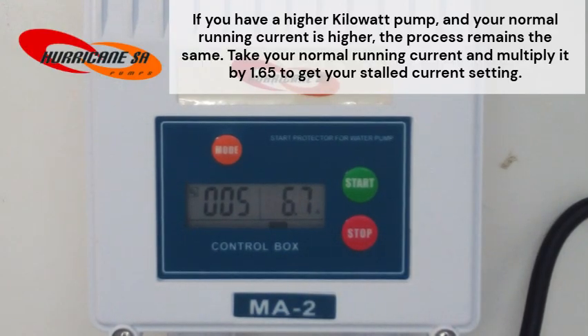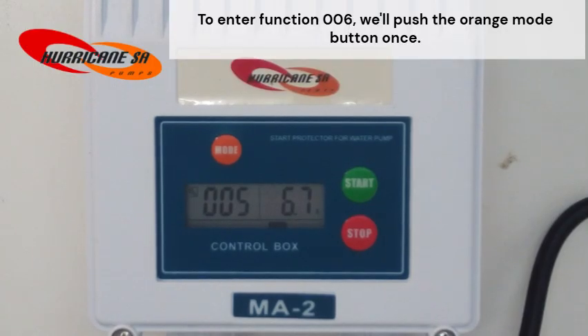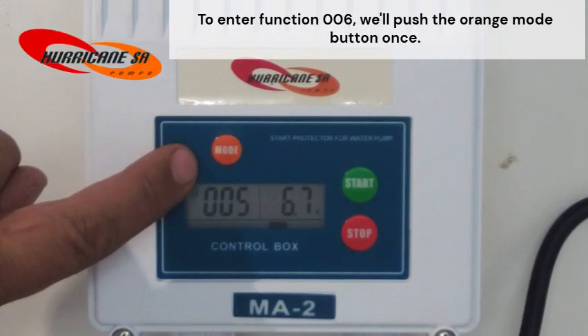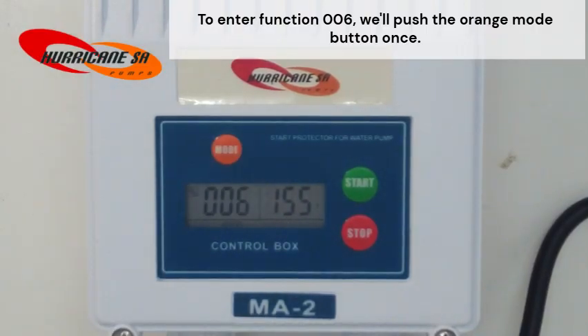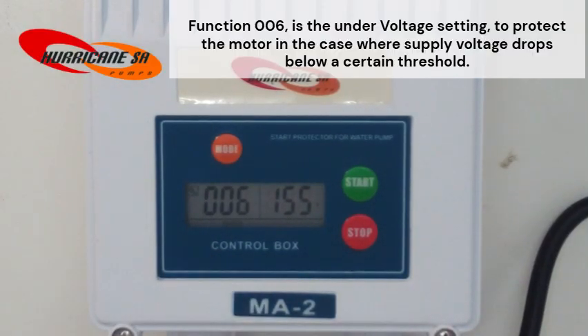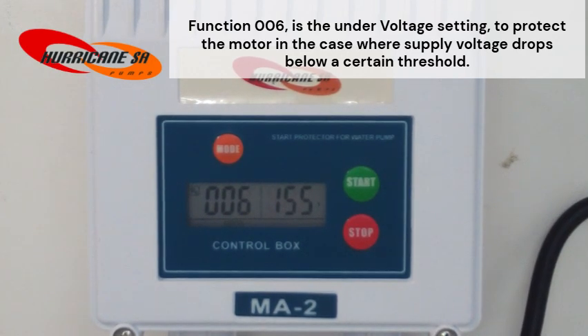If you have a higher kilowatt pump and your normal running current is higher, the process remains the same. To enter function 006, we'll push the orange mode button once. Function 006 is the under voltage setting to protect the motor in the case where supply voltage drops below a certain threshold.